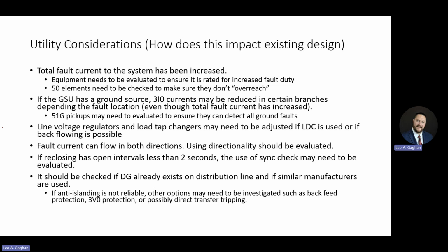And then lastly, it should be checked to see if distributed generation already exists on the distribution line, and if they are from similar manufacturers. That's becoming a pretty typical check, right? We want to make sure that multiple inverter manufacturers are going to be out on the same circuit. Because if that was the case, then they may hold each other up and prevent the anti-islanding functions from operating. And if that is the case, we may need to consider direct transfer tripping. So that would be a situation where if the breaker at the head of the feeder were to trip, it would automatically send a direct transfer trip to those reclosers at the IBR location to take them off of the circuit and prevent that islanding occurring. So these are all considerations that need to be thought through.